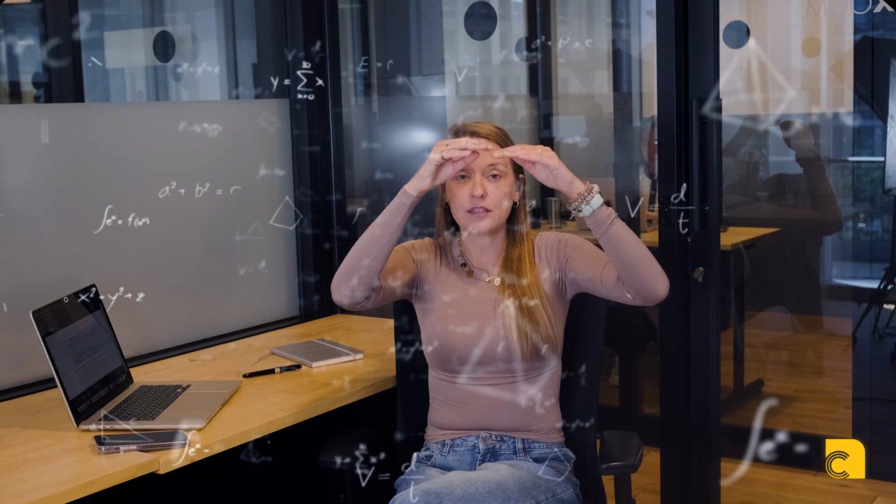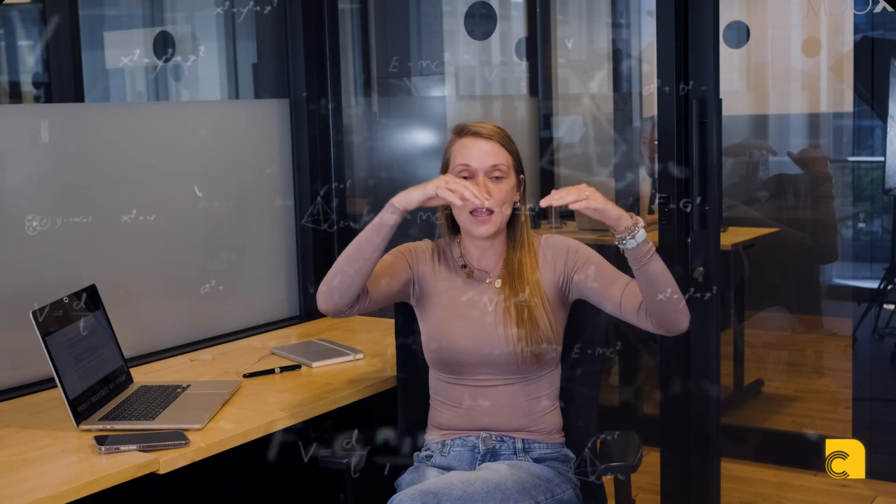Now, what an advanced control system does is it will calculate what the theoretical hydraulic max is, and then execute an algorithm or a series of algorithms to bring the set points to bring the flow rate slowly up to what that is. Same as the mental model a human would be doing.